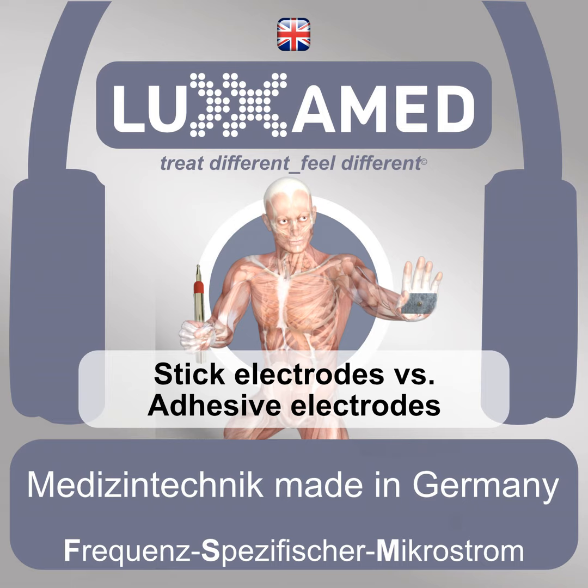Then we have more applications. Of course, we have the wet towels. That is, you take a towel and moisten it or soak it in water to act as a big electrode. So the full towel is wet, and you put it on some places, like here you can see on the cervical spine or on the face, and down you can make something like a liver wrap. You can cover large areas of the body with this towel, which is acting like a big electrode. But also in our point of view, it is not really recommended, because here is the potential that you get contact with earth parts, or with a dangerous voltage because of the big size of the towel, and it's quite wet. If it's too wet, it's dropping down and something like this. So it is quite unsafe to use it in that way, just for your information.